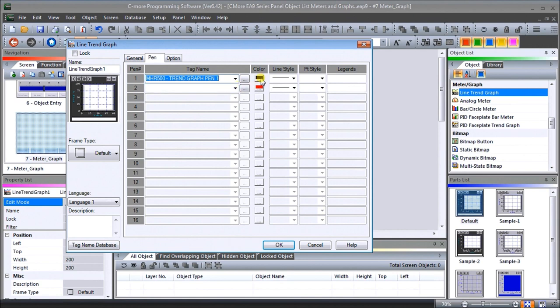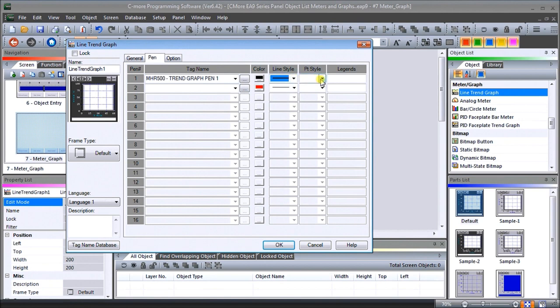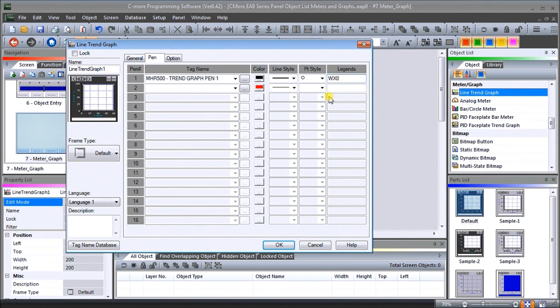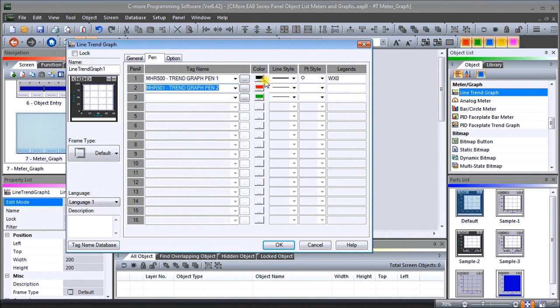We'll leave pen one at the color black, make it a little thicker so we can see it. Our point style will show a round circle at every point on the graph. For the legend, we'll call this WX0 — that's our PLC point we're going to graph. Pen number two we'll put in red, change it to a fixed line with a triangle point style, and set it to WX1.